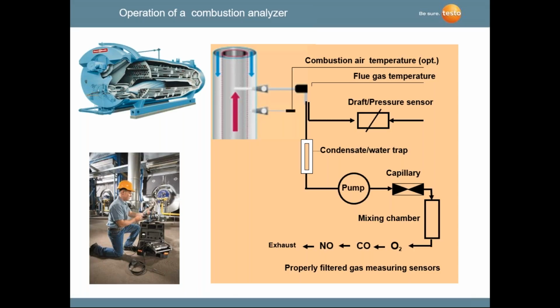So, when I talk combustion analyzers, I talk either 2-gas or 3-gas or even more. When I say 2-gas, that means that we can measure oxygen and carbon monoxide. If I say 3-gas, then we're measuring oxygen, carbon monoxide, and NOx. And you can see by that diagram that we have to have a good seal. We can't have any leaks in our probe and hose assembly as it enters into the analyzer, because it has to go into the 2 or 3 or 4 sensors of the analyzer to get your measurement readings.